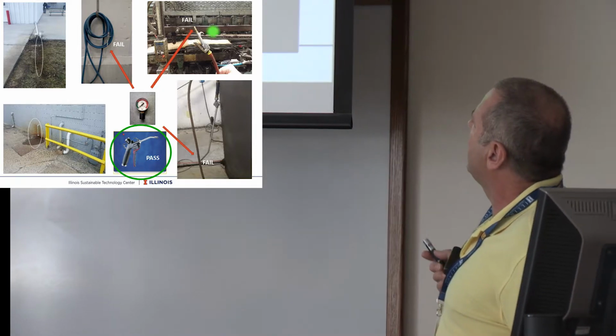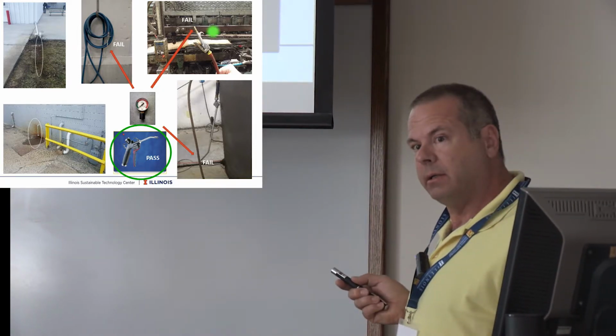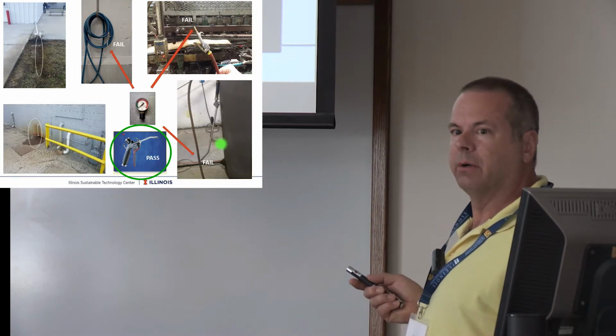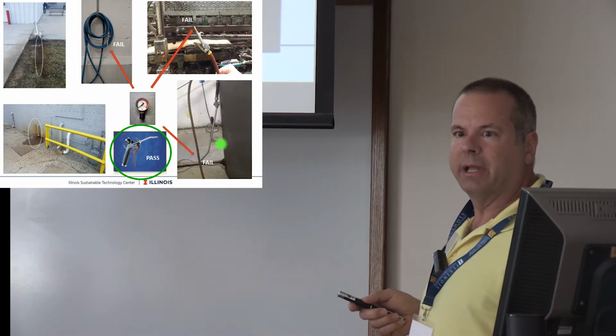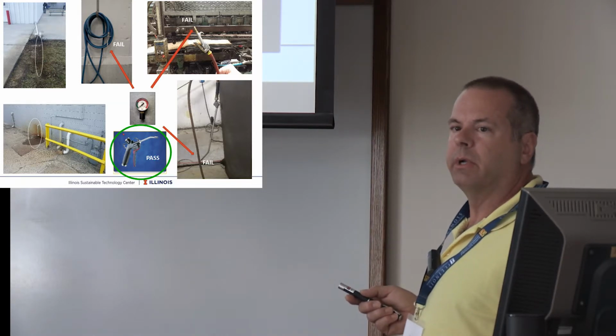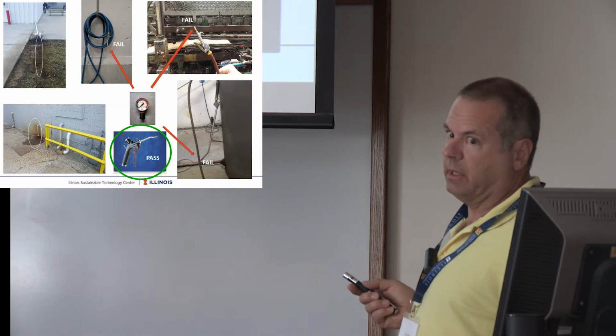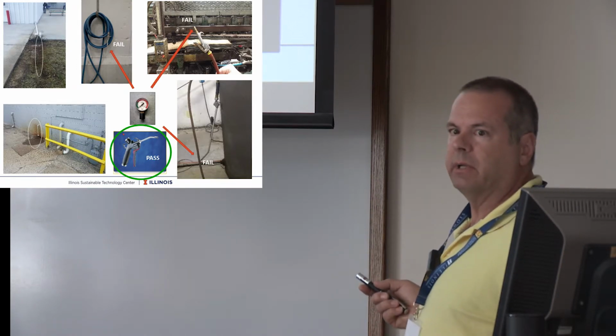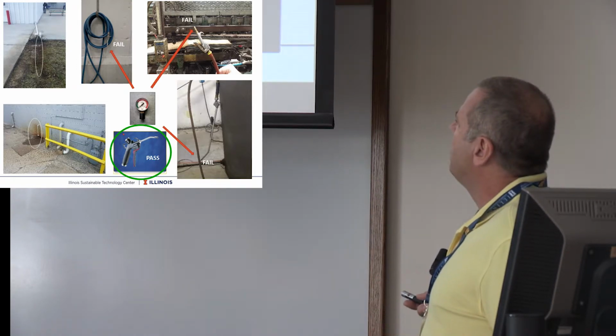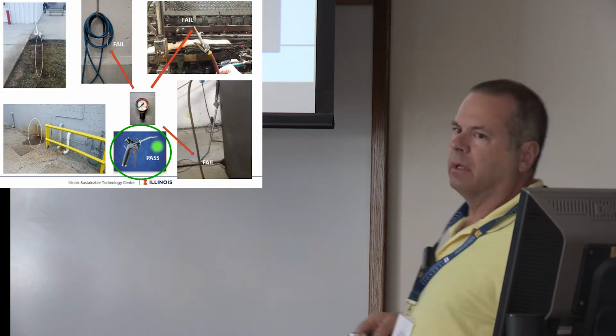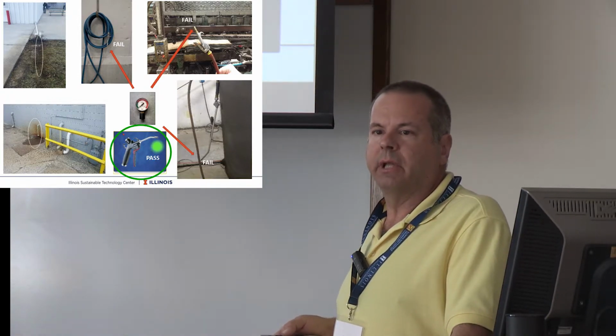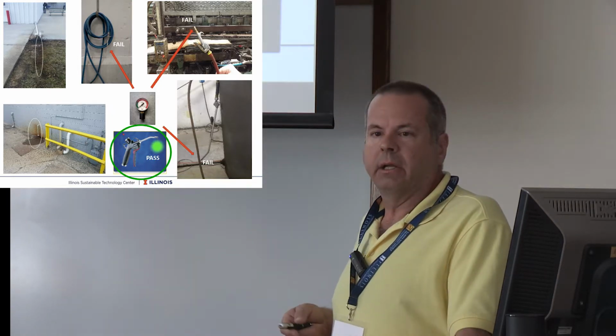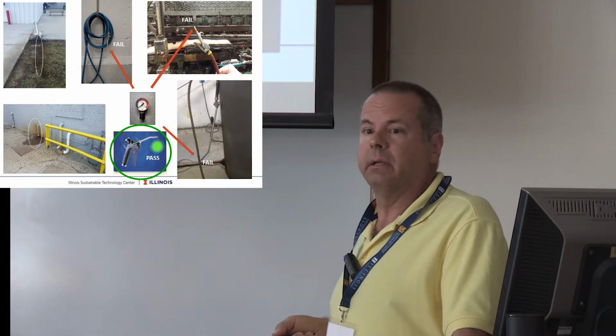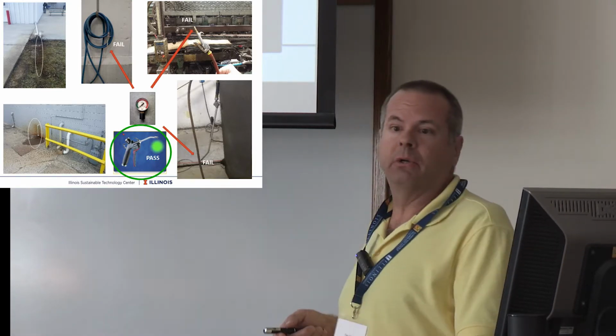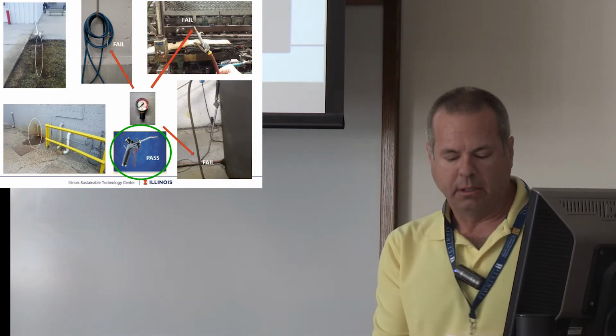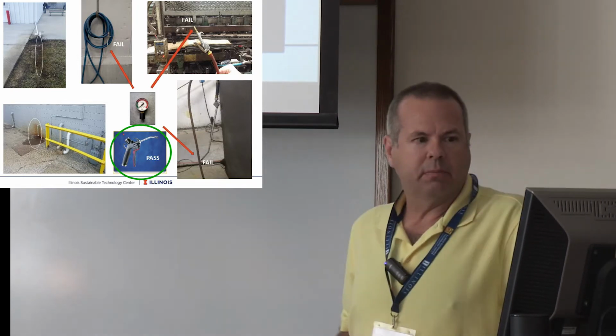These are air guns people have modified, either brought in from home or modified themselves. They're basically open tubes, which are not OSHA compliant - not safe for a number of reasons like air injection and noise. We recommend instead using high efficiency safety guns, which pass your OSHA gauge tests, cut noise down roughly 50%, and also save between roughly 20 to 30% energy. Those are good options.